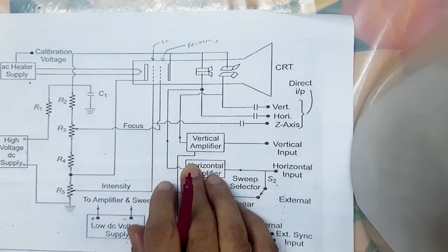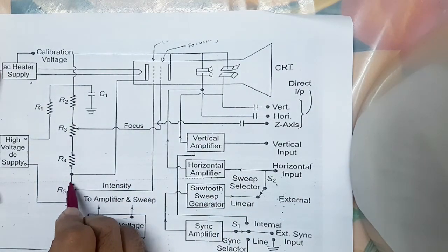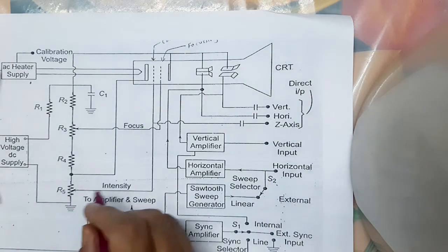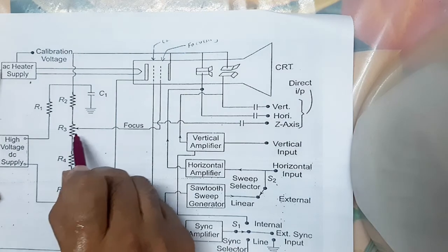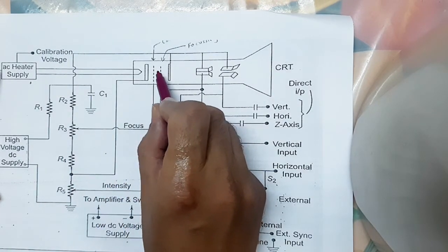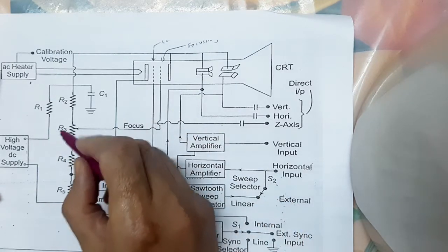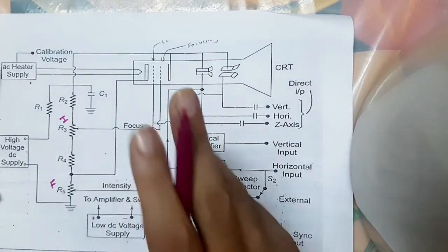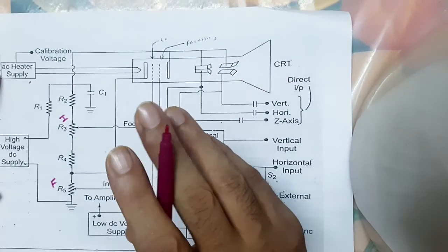This is our intensity control. If we increase or change the voltage here, more voltage is given to the control grid, so we can increase or decrease the intensity. Similarly, R3 is connecting here so we can change the focusing — we can focus the spot on the screen of the CRO. So there are two variable controls: the intensity control and the focusing control. These intensity and focus control knobs are given on the front panel of the CRO.